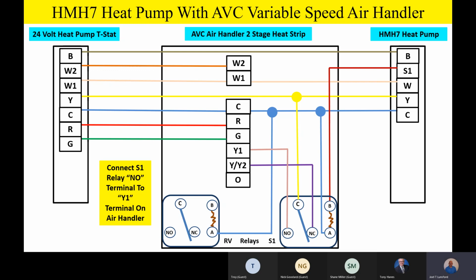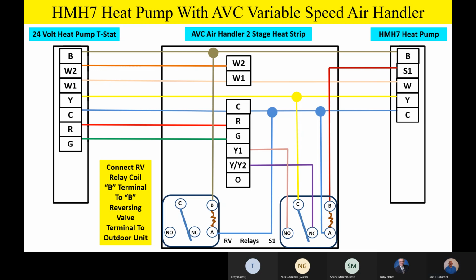So this looks real familiar to everybody, because this is what we've essentially done with every single relay scheme that we've looked at so far for switching our low airflow. We're going to do the same thing on the variable speed air handler. But now that RV relay, that's a little different thing. What we're going to do, we're going to take the other side of the relay coil. So one side of the relay coil on the RV relay goes to common. The other side goes up and grabs the B terminal, the B wire going outside for the reversing valve.